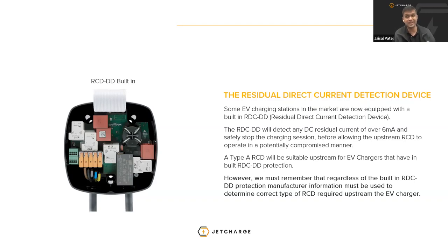And if it does not, or if you cannot confirm that they have the RDC-DD, you should specify what's called a type B RCD, which has an implication on your distribution board, because a typical type B RCD cannot fit on a typical MCB chassis. So you would have to have a DIN rail to mount your type B RCD onto, whereas a type A RCD will be able to fit on a typical MCB chassis. So that is something to consider.